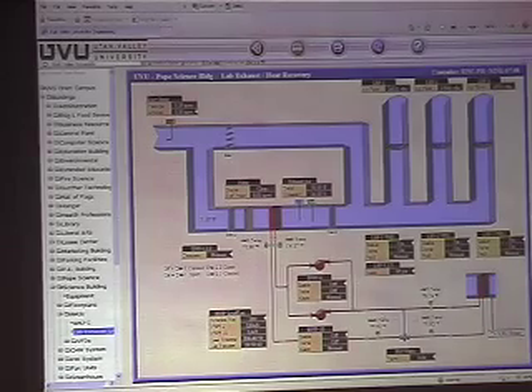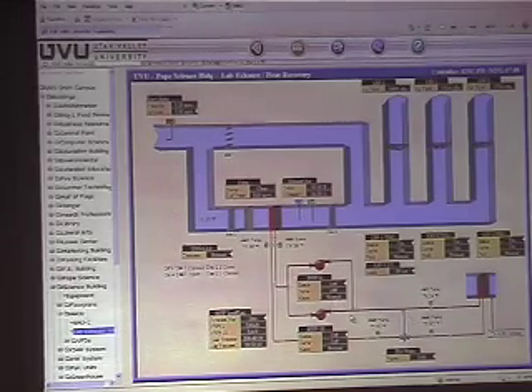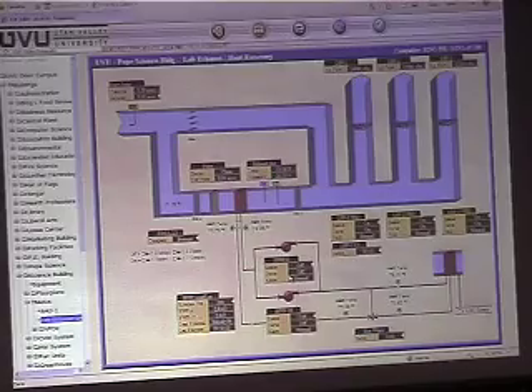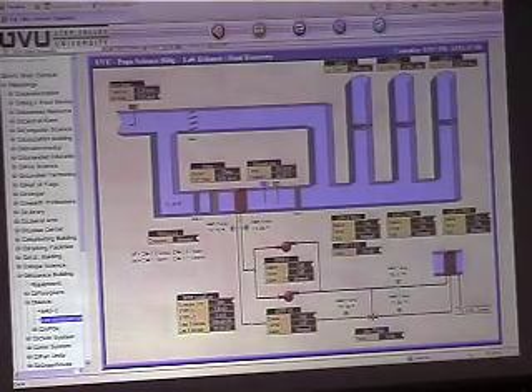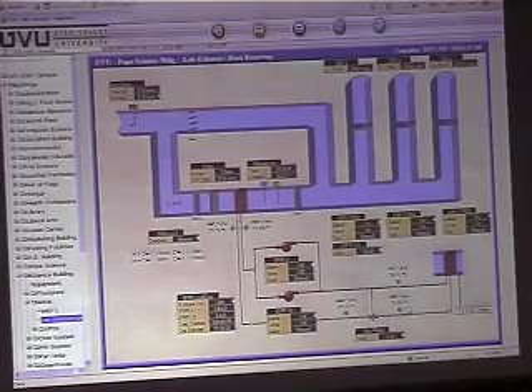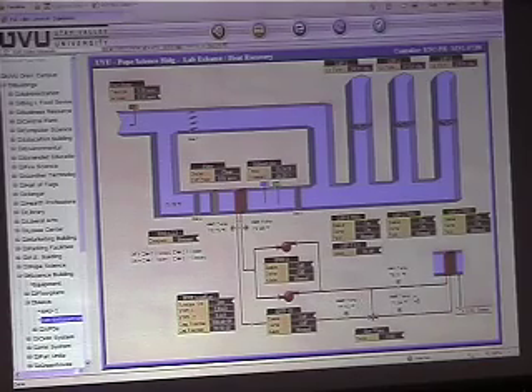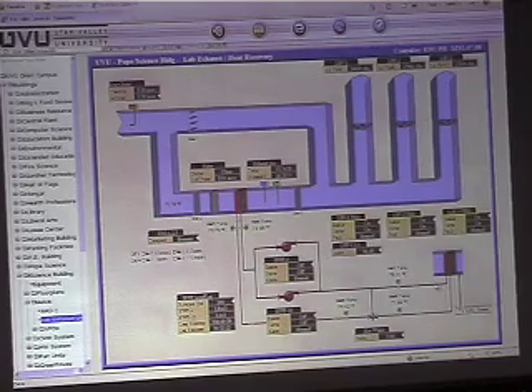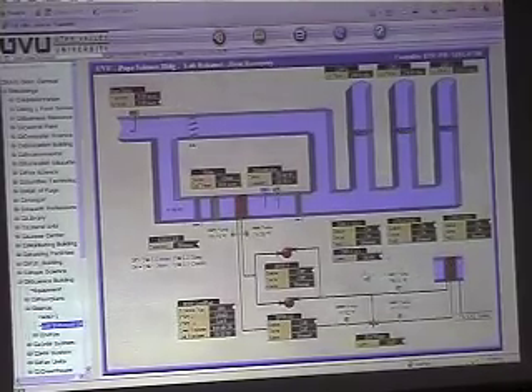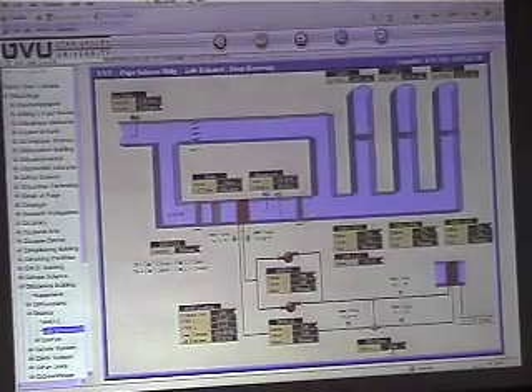This part of this heat exchanger portion here only runs when we're running the outside air fan on the air handler. So this allows the air to be tempered coming in from outside. So we're taking advantage of the heat that we're exhausting out of the building and transferring that back over to the air handler without exchanging air. So when the outside air fan kicks on, one of these two pumps will turn on. As you can see, we've got a lead lag schedule here for those. And they'll circulate water either through the coil or they'll bypass it, trying to maintain 48-degree discharge off of this coil here. So that we still provide cooling to still take advantage of the free cooling on the outside air. So that's what controls the modulation of this valve here.